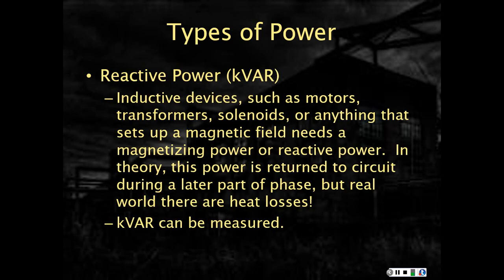And then finally, as we discussed last time, certain devices or loads within a building, ones that require setting up of a magnetic field, in particular motors, transformers, solenoids, actually have to have a magnetizing power or reactive power. And again, in theory, that power is returned to the circuit when the phase goes in the opposite direction, when there's a phase change. But in the real world, there's heat losses. So in transformers, motors, all those things, part of the power that's given to it to set up the magnetic field is lost. It's not given back to the circuit. And reactive power, or kVAR, can be measured.